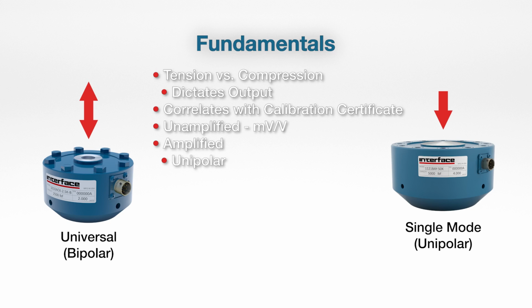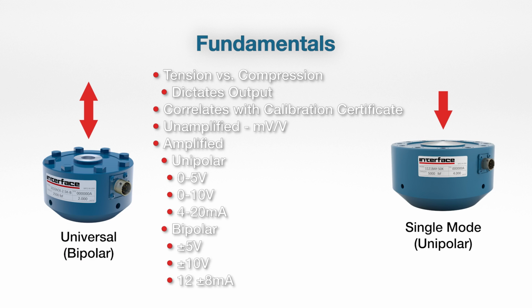So, load cell fundamentals. Essentially, you're going to use the load cell in one of two ways: either bipolar, for universal application, using it both in tension and compression, or in a single mode, either only tension or only compression, and that's going to dictate what output you get from the load cell. Most of our load cells are going to be a tension upscale device, meaning you're going to get a positive output when a load cell is placed in tension. And so also correlate that with your calibration certificate as previously referenced.